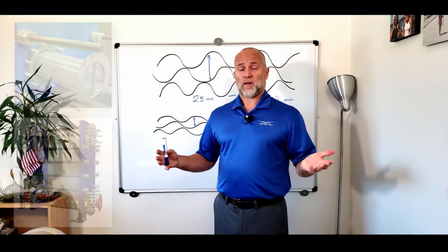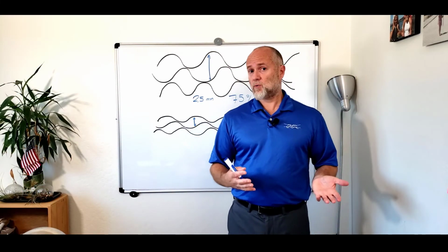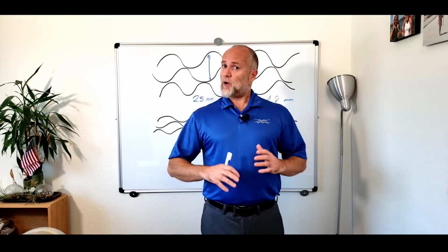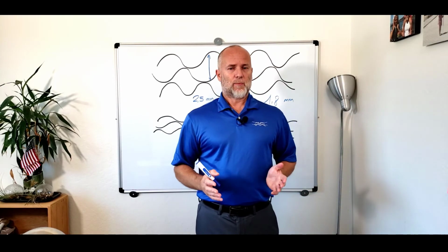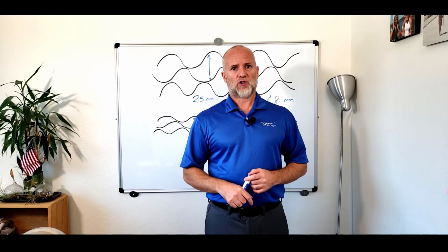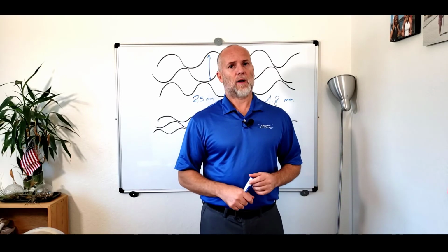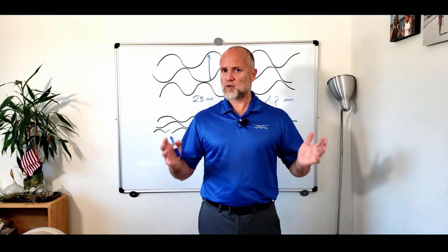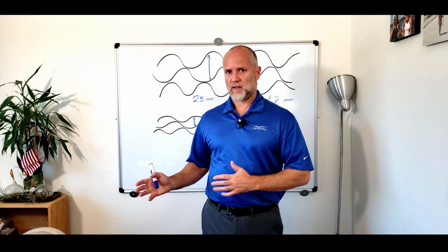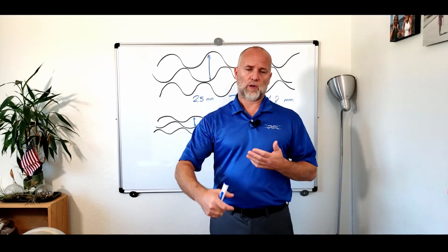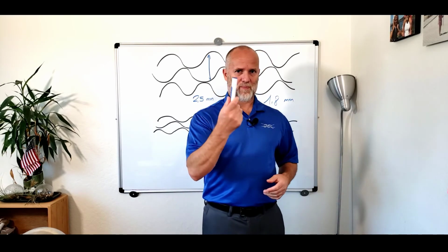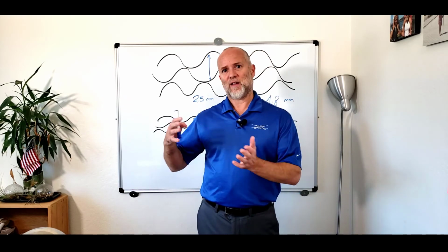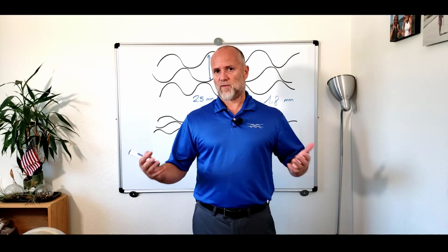That's it, essentially. Important to remember, to close this video, is that about 90% of the large debris that you have in your heat exchanger comes at startup. When you have a new system, you have all the contaminants, the washers, paper clips, pans, hats, whatever, that are in the piping, particularly if you have fairly large piping.